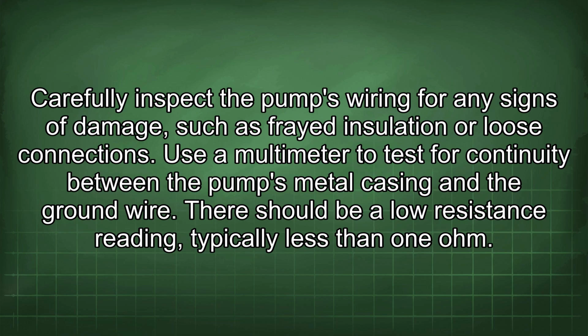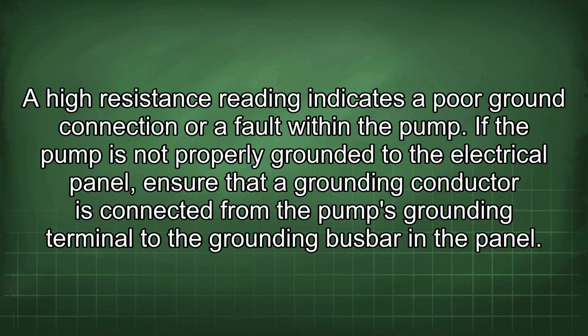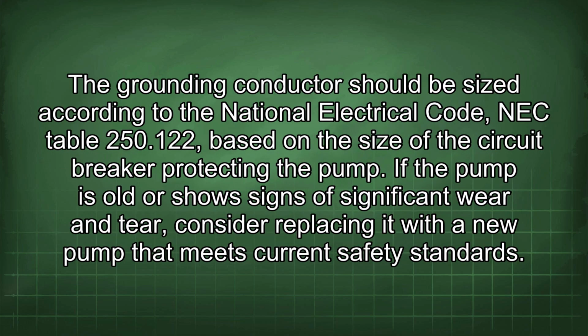Carefully inspect the pump's wiring for any signs of damage, such as frayed insulation or loose connections. Use a multimeter to test for continuity between the pump's metal casing and the ground wire. There should be a low resistance reading, typically less than 1 ohm. A high resistance reading indicates a poor ground connection or a fault within the pump. If the pump is not properly grounded to the electrical panel, ensure that a grounding conductor is connected from the pump's grounding terminal to the grounding busbar in the panel. The grounding conductor should be sized according to the National Electrical Code, NEC Table 250.122, based on the size of the circuit breaker protecting the pump. If the pump is old or shows signs of significant wear and tear, consider replacing it with a new pump that meets current safety standards.